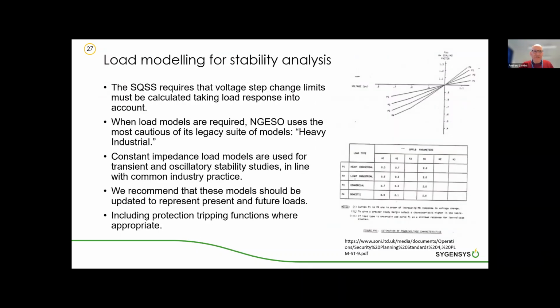So in GB studies, the Security and Quality of Supply Standard, the SQSS, requires that voltage step change limits must take load response into account. And this is a graph from the present sort of load models that are still in use. And yes, it does come from the days when we drew graphs by hand. When load models are required, ESO uses the most cautious of this legacy suite of models, one called heavy industrial, which produces the most pessimistic results.